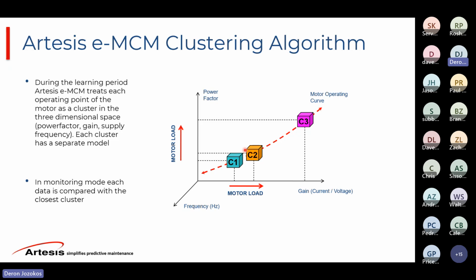Now, if it sees a new operating parameter, you can always update the algorithms and let it learn for another day and a half, and it'll see something different. A good example is maybe that cooling tower learned during the summer, with real high loads and different operating parameters. But now you're in the winter and it's cooler, much lighter loads, and it's not running as often, and it may not have a cluster built for those particular operating parameters. So it'll see it as different, but it doesn't fall into any default categories. So you simply hit the update button on the software, and it builds more math models. So over time, this thing gets more and more intelligent.